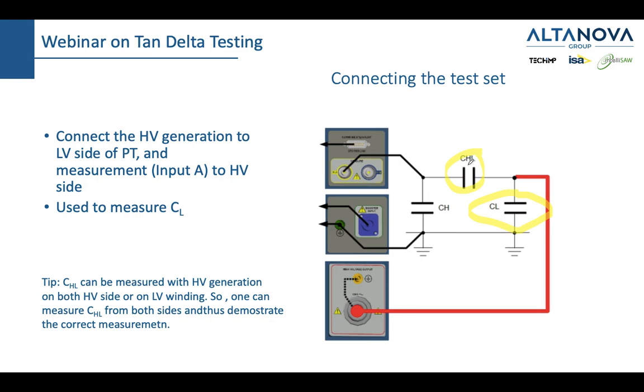It's not that this is necessary, but I'm giving you some tips and tricks in order to be sure that you are doing the test correctly in case there are some issues. In the past, the tan delta measurement was pretty difficult because we needed to measure very small values like today, but analog circuitry was more prone to noise. Today, we're not facing such issues, but regardless, it is something which should be taken into consideration.